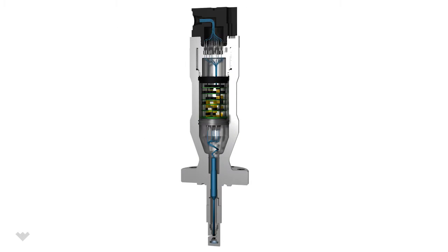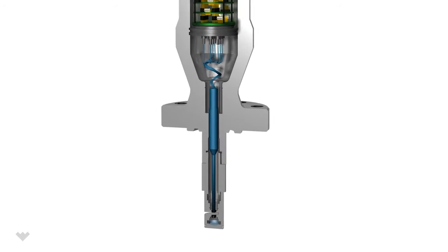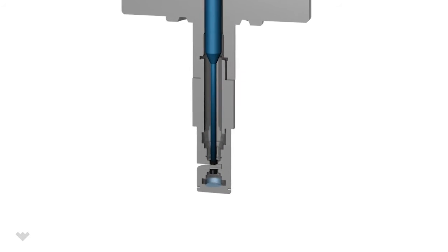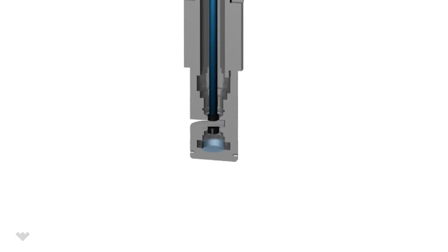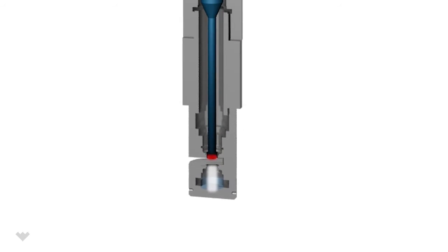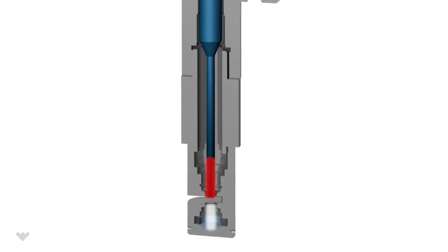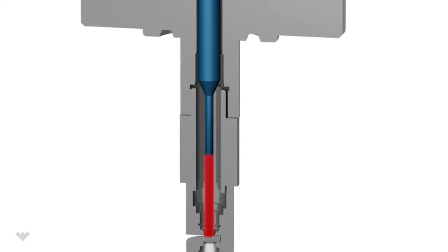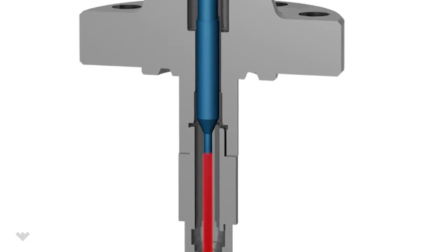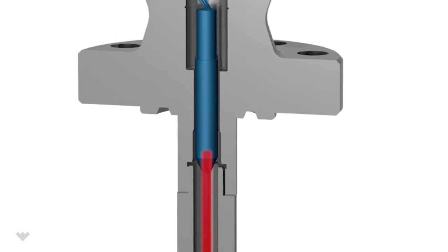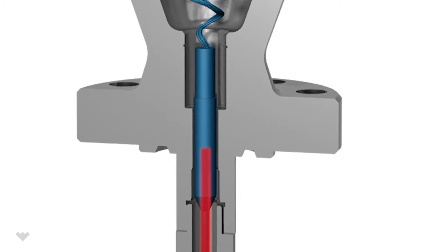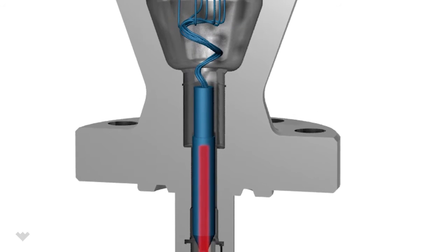The meter uses a broadband near-infrared optical source and sophisticated optical filters to measure transmission at key wavelengths, where oil and water have very different absorbance.